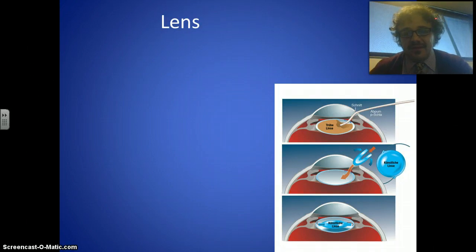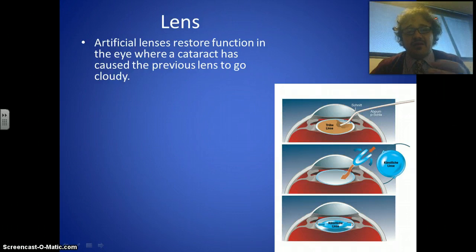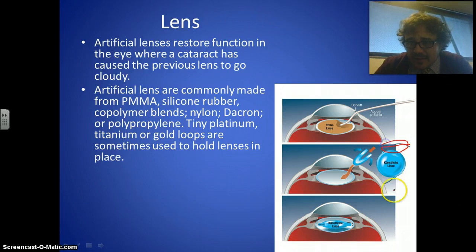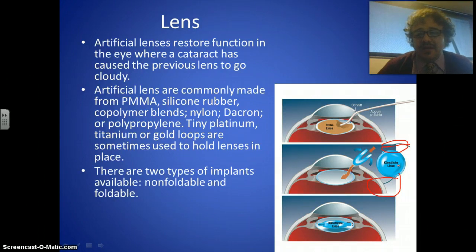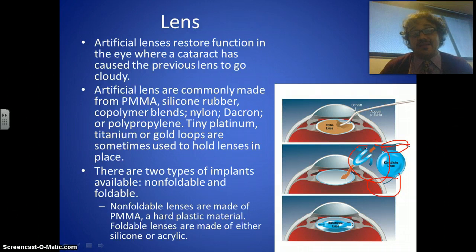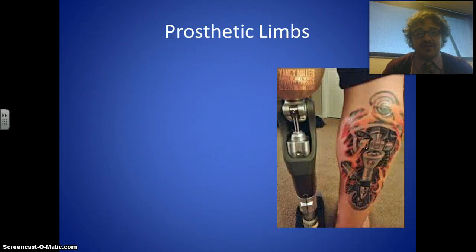Artificial lenses restore function to the eye when a cataract has caused the natural lens to go cloudy, blocking light from passing through. They're commonly made of PMMA, silicone rubber, or copolymer blends — including nylon, Dacron, and polypropylene. You can see the little loops that hold the lens in place. There are two types: non-foldable, which are PMMA hard plastic, and foldable ones made of silicone or acrylic. Foldable lenses are cut, folded in half, slid through a small incision, and then pop open inside.